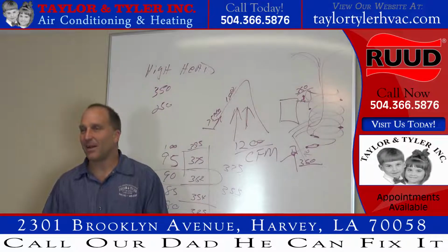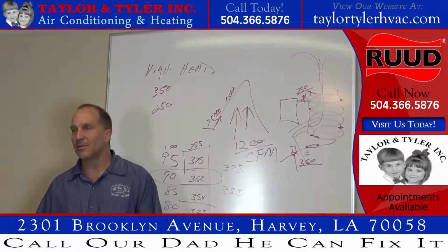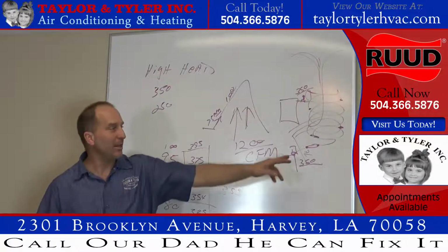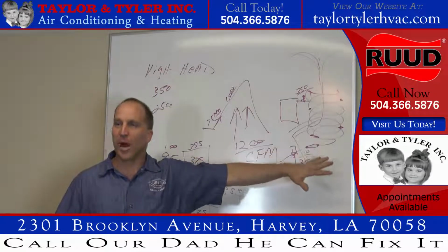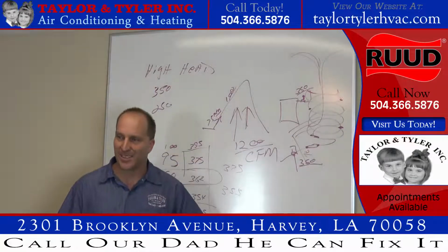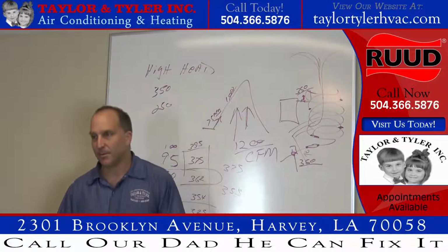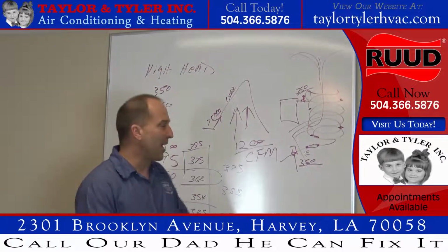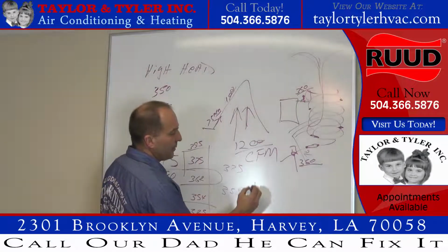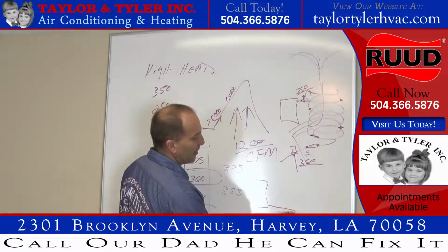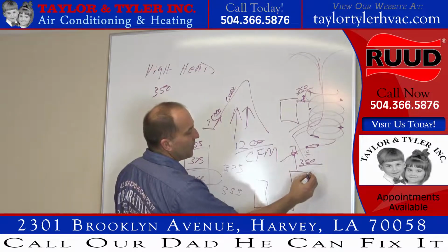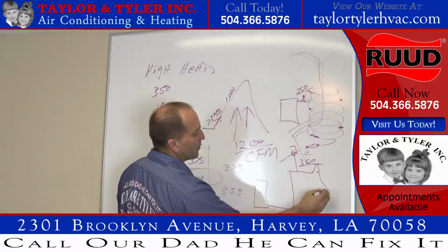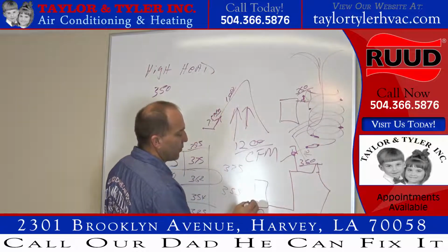But how do you find that, guys? Unless you understand superheat and subcooling, and unless you understand temperature differentials and drops, when it drops in pressure and it drops in temperature, there's your restriction. Okay? So if you got a high side line, and there's your condenser, and you got a high side line, comes up your wall, goes over to your evaporator coil, and then comes back down over again into your compressor, okay?